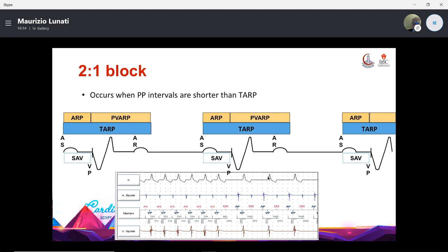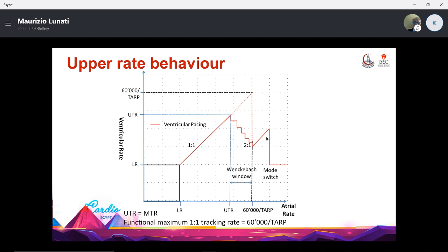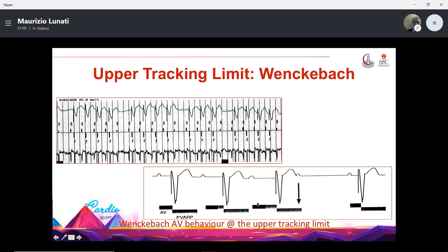In order to avoid this fall from 1 to 1 to 2 to 1, the manufacturer developed a system which gives a so-called Wenckebach period before the appearance of 2 to 1 pacing block. And this is an example. The patient's rate increases, and there is a Wenckebach behavior before reaching the upper tracking limit.